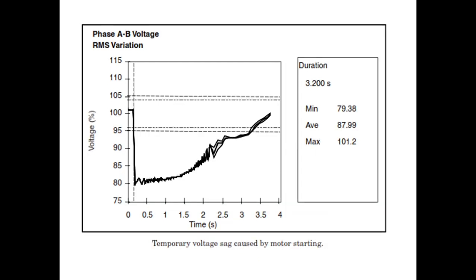Then we are going to see the temporary voltage sag caused by motor starting. If you think about the induction motor, or any motor, at starting it will take more current. When it takes more current, there are chances that the voltage goes down. That is called a temporary voltage sag. You can take any motor, such as an induction motor or DC motor. At starting you will get a higher current, and if you are getting more current, ultimately that is going to affect the voltage also.